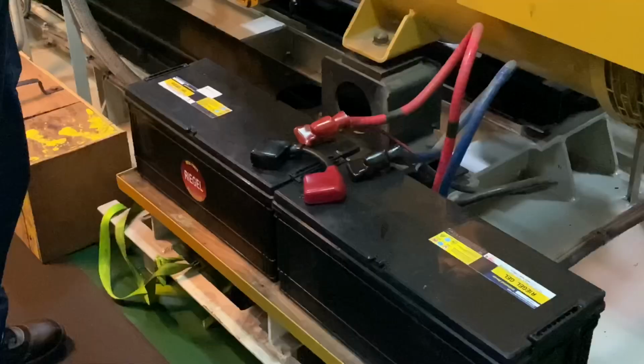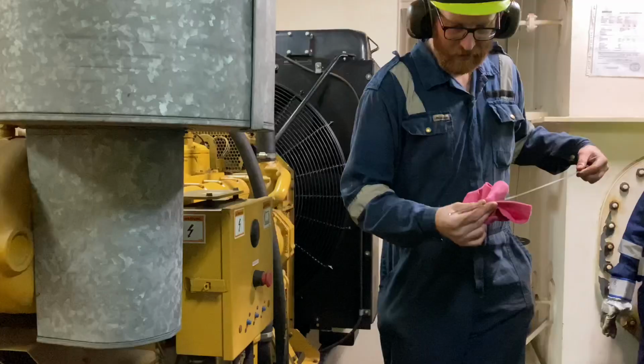which is to wait. We have an emergency generator which is supposed to take over in not more than 45 seconds. That is the rule. So you just need to wait for 45 seconds and this emergency generator will run automatically. And of course, if it fails to run automatically within 45 seconds, then it will be a different scenario, and I am going to share how and what to do in case this one fails. But for sure, if you are checking it weekly, doing the maintenance and all the PMS jobs on this one, then you don't have to worry. For sure, this system will run automatically.